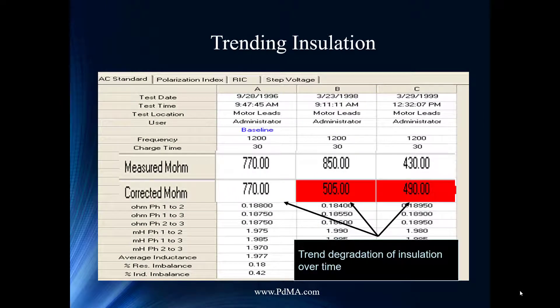When we trend insulation data, you can clearly see the value of temperature correction. The raw measured megaohm values jump around — 700, 800, 400 — all due to temperature changes. But the temperature-corrected value shows a nice, consistent downward trend. We always look at the baseline first, and if there's a change of 10%, 20%, or whatever threshold you set, we highlight that in red so you can investigate further.